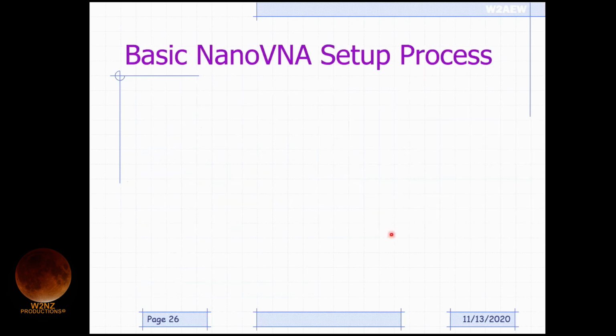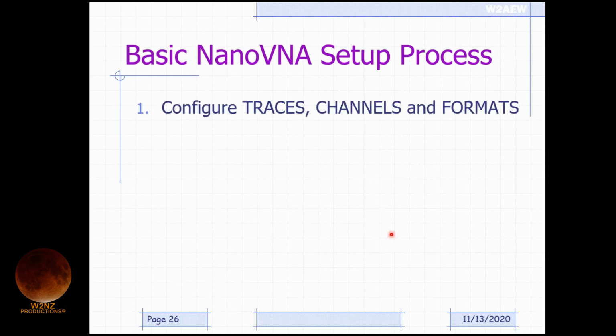So here's the basic setup process to actually use the NanoVNA. You set up and configure what traces you want on. How many traces do I want to look at? Maybe I just want to look at SWR, or maybe I just want to look at my S21 parameters, or whatever it might be. So tell it how many traces you want on and what channels those traces are on. The channel determines whether you're making a reflection measurement or a transmission measurement for that trace, and then what format those traces are. Then you set up the stimulus frequency range. Those two things can be interchanged. You can start off by setting the stimulus and then configure the traces and channels, but usually those are the first two steps.